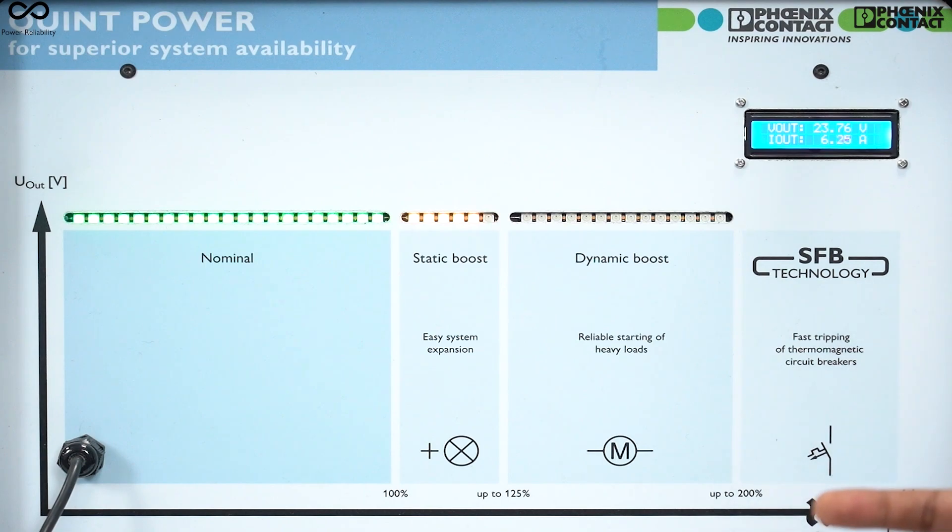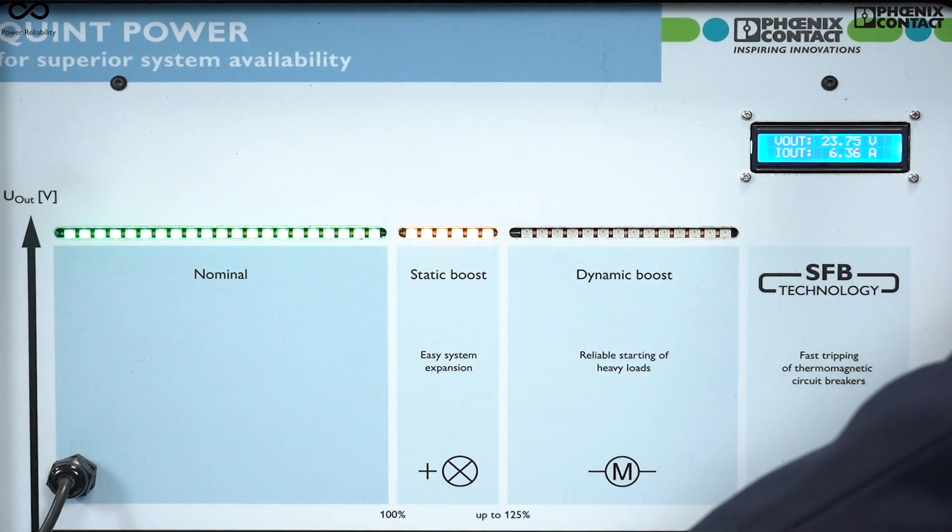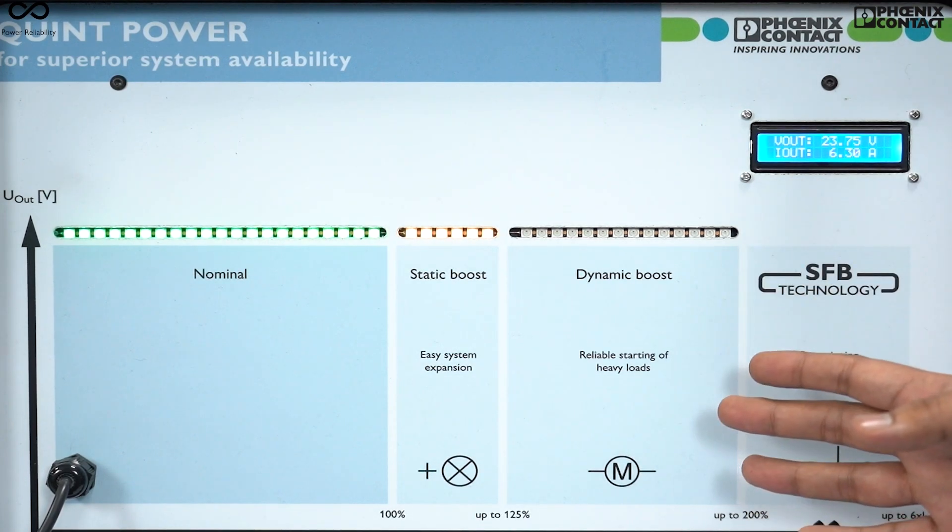If I make this power supply work in dynamic boost condition, this power supply is now providing 10 ampere of current and it is only limited for 5 seconds. In dynamic boost feature, the power supply will give you 200 percent of the rated value. That means here 5 ampere power supply will provide 10 ampere of current for 5 seconds. This dynamic boost feature is required to start reliably your heavy loads.